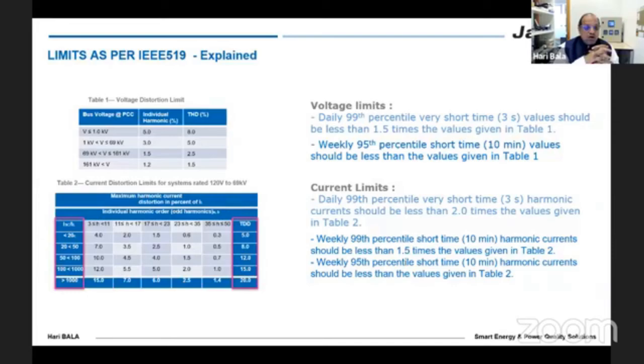If you look at it, the limits are basically done like that. For the voltage distortion, for every voltage level, we have an individual harmonic percentage, created as a table. For current as well, for example, I have put the current distortion limits in one table, for 120 volts to 69 kV. Here on the right side, you have the ISC by IL value.